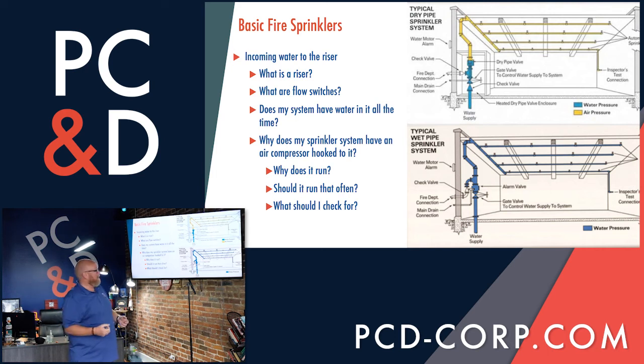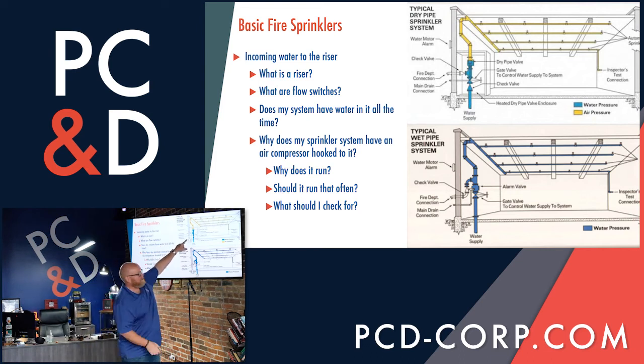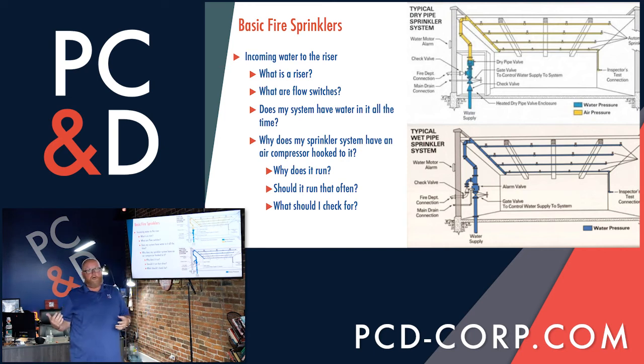So, good question. We all had to learn this at one point in time, including myself. Why do you have a dry system? If your pipes, like on this system here, go into your attic, and you've got pipes running through your attic that are possibly exposed to cold weather, and we want to avoid freezing, typically that is the main reason and the only reason that you would ever use a dry system. So now you might be asking yourself, well, if the lines are full of air, how do you put the fire out? Another great question.